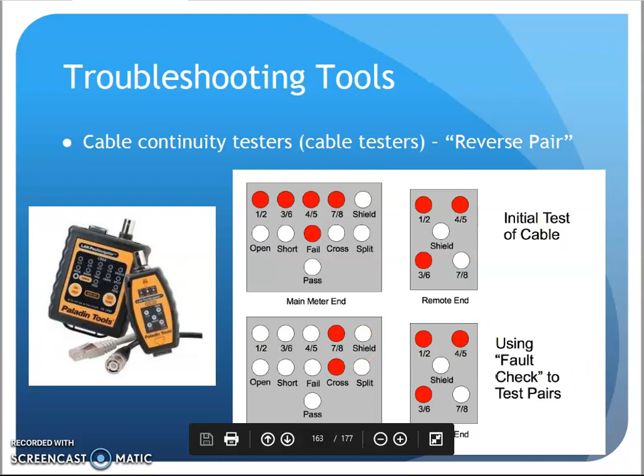If I have a short, again, I go through the fault check, and it might show, hey, this 1-2 pair is shorted. Come over here to reverse pair: if 2 wires are flip-flopped in location, it's going to say 7-8 got flip-flopped, the brown pair on the end of my cabling. So this is going to give me a clue as to what might be wrong.